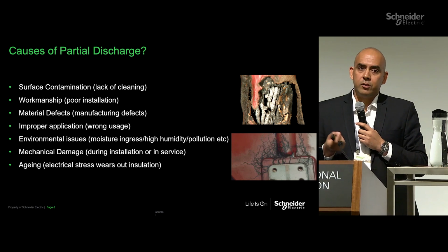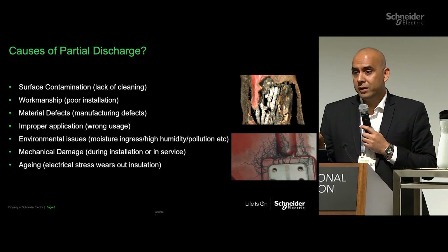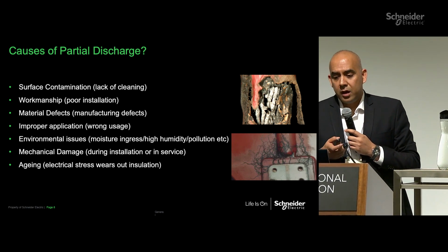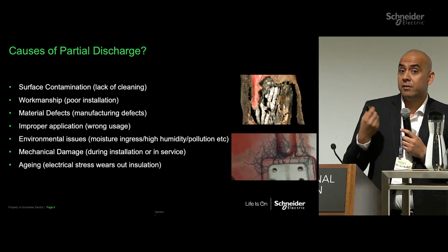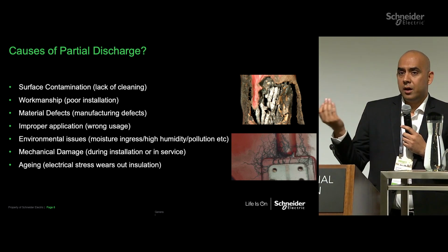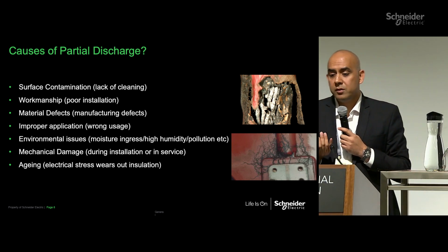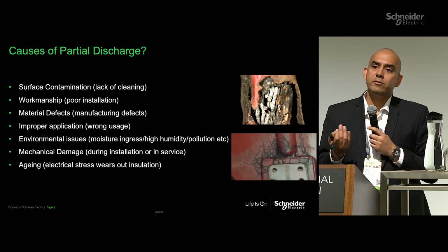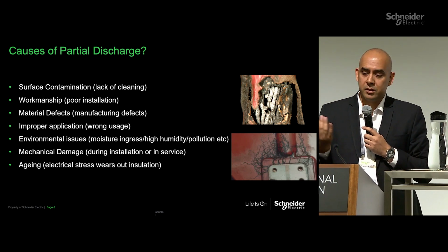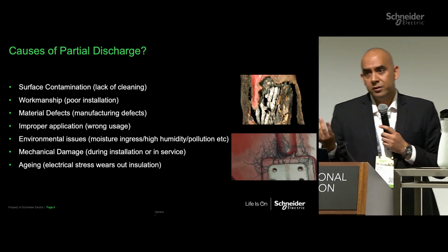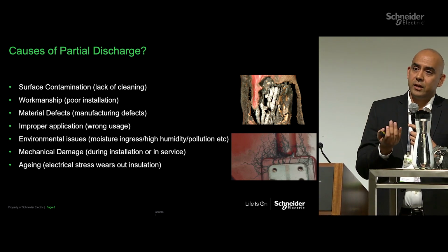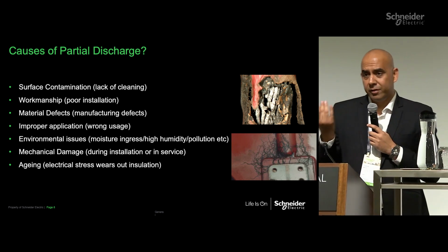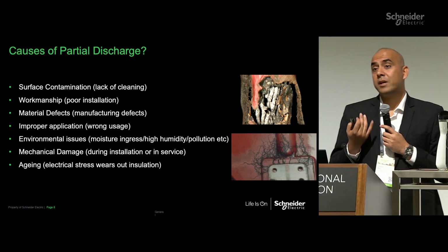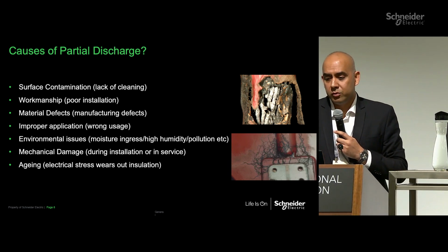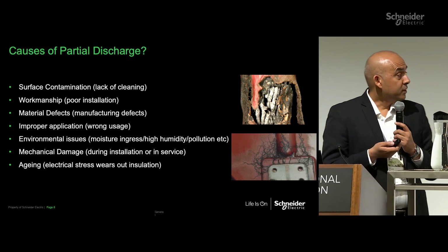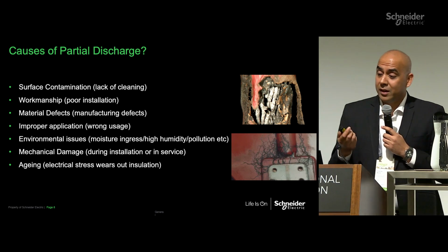There could be wrong usage, when you're applying the equipment wrongly, in a different application. Moisture ingress is again a reason because of environmental conditions, pollution, or any mechanical damage which happens during installation or during service, or of course aging, because aging can also create this because of the electrical stresses, etc., which is happening, and the systems can go down. And of course, you can have issues like these coming in insulators.